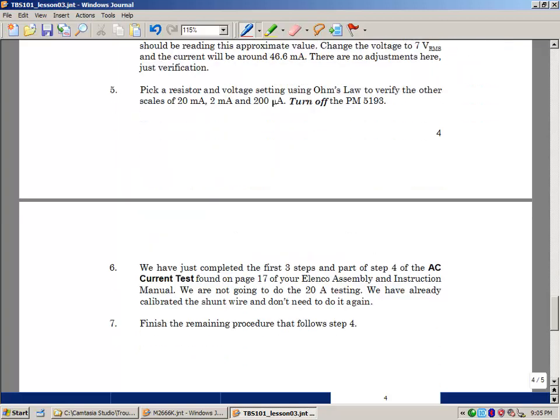There's another section in the instruction manual about a high current test for AC, checking that the shunt wire is working correctly. But we don't have to do this since we've already calibrated the shunt wire, and it's also pretty dangerous to work with, so we're going to postpone that for now.